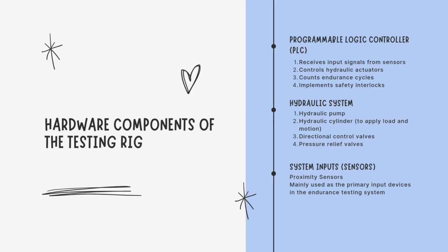Next, the hardware components of the testing rig. First, the PLC. It receives input signals from the sensors, controls the hydraulic actuator, counts endurance cycles, and implements safety interlocks. The second one is the hydraulic system itself. It consists of a hydraulic pump, cylinder, directional control valve and pressure relief valve. And the last one is the system input, which is mainly a proximity sensor as the primary input device.